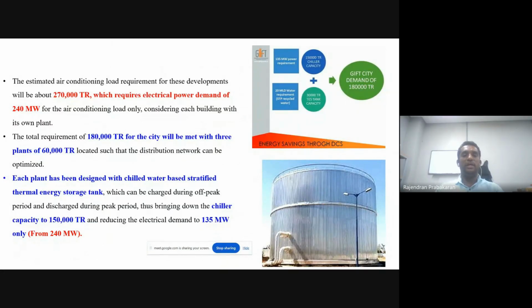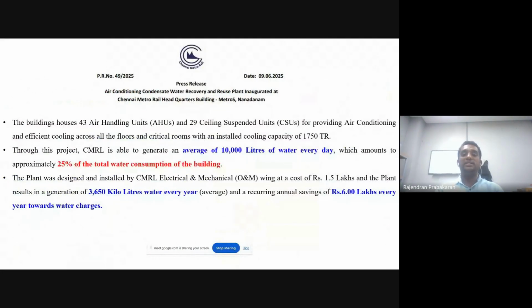Here a stratified thermal energy storage tank was used, which was charged during the off time and discharged during the peak time. With this, the system capacity again got reduced from 180,000 to 150,000 TR, and electrical demand also reduced to 135 megawatts as compared to 240. So this was successfully installed in Gujarat. And the second one is in Chennai.